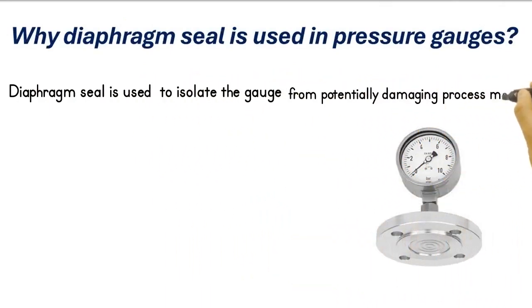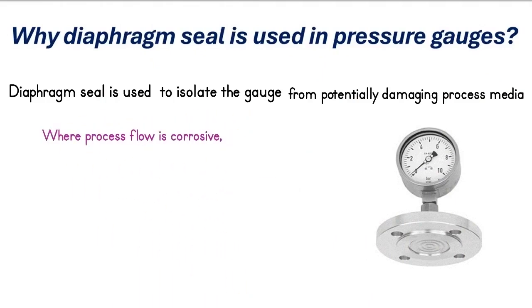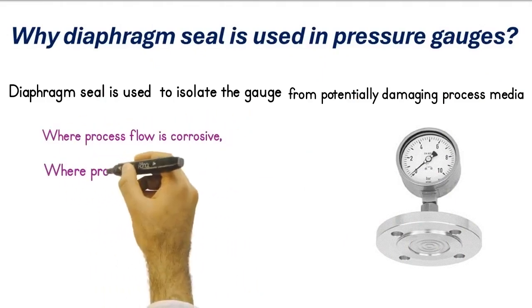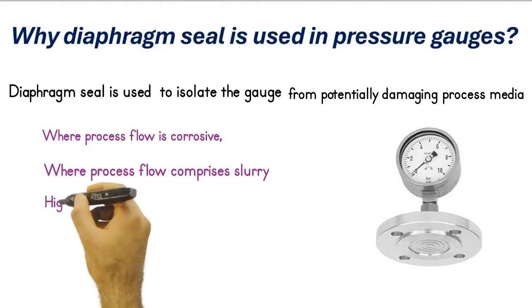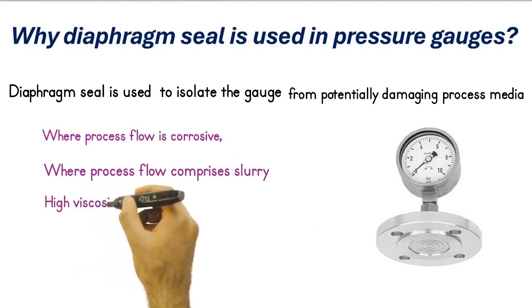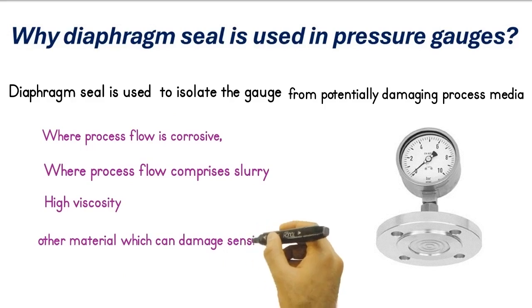Why is a diaphragm seal used in pressure gauges? The diaphragm seal is used to isolate the gauge from potentially damaging process media — for example, where the process flow is corrosive, or where the process flow comprises slurry, high viscosity, or other material which can damage the sensing element.